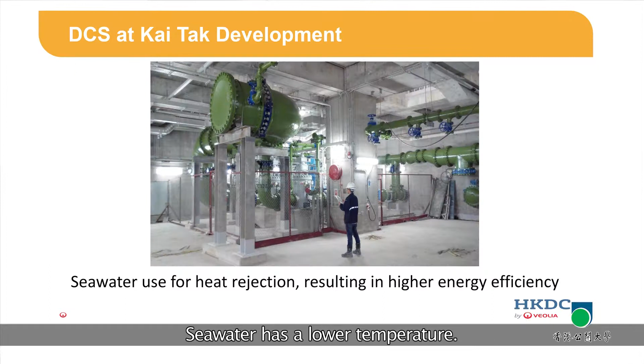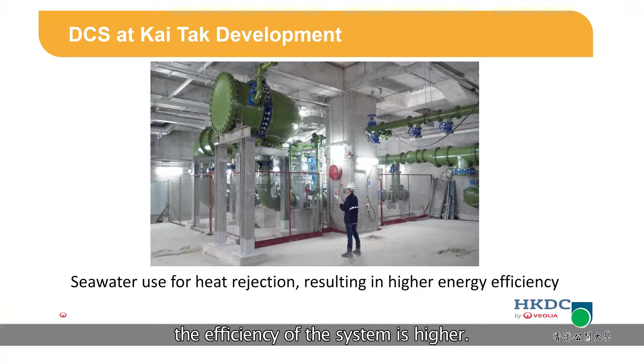One characteristic of this project is you use seawater. Seawater has a lower temperature, and if the condensing temperature is lower, the efficiency of the system is higher. This is one reason the government wants district cooling using seawater, and this technology is difficult to use with individual buildings. Let's look at other places like Singapore, Guangzhou, or the Middle East.